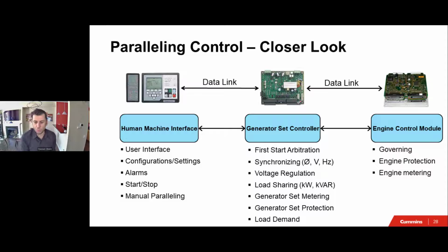You might ask a question: what if I have generators of different sizes, a 1 megawatt, a 2 megawatt, and a half megawatt? Can a controller load share equally? Yes. The genset will share the load proportionally amongst the generators. So the larger the generator, the more load it takes. So at the end, percentages will be equal across all generators. Generator set metering, generator set protection, and the capacity to load consumption are also part of the genset controller. And then that talks to the engine control module, or the ECM, right? Your car has one of those as well. And that ECM is responsible for the governing, the engine protection, and the engine metering.